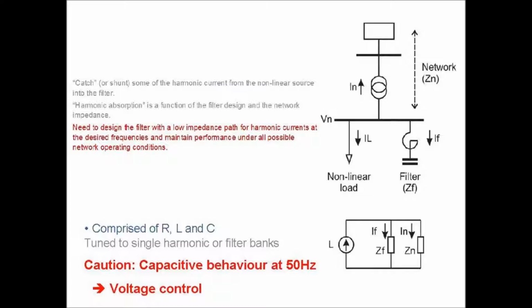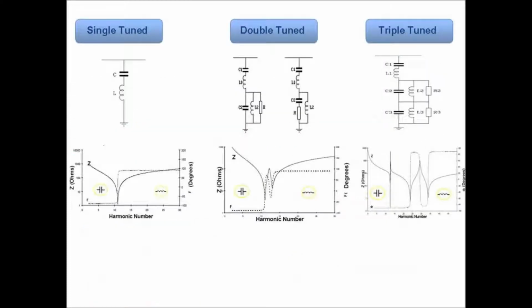And you have to remember one thing. Filters are made of RLC. The capacitive part of that filter can change your voltages at 50 Hertz. So you need to make sure that you tune your filter accordingly. Otherwise you can have unwanted voltage control, and your voltage will be increased above 110 kV and possibly significantly so. This is just kind of an idea of all the different types of filters out there.